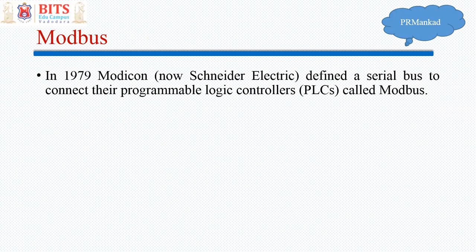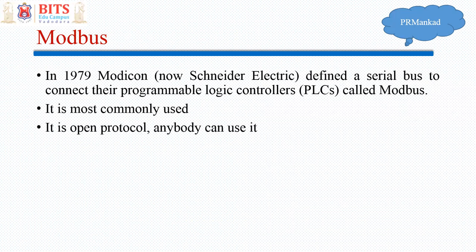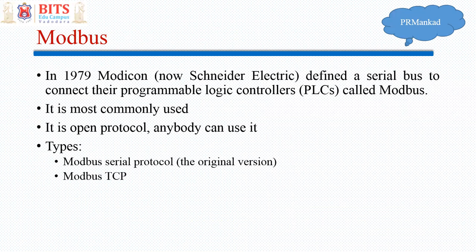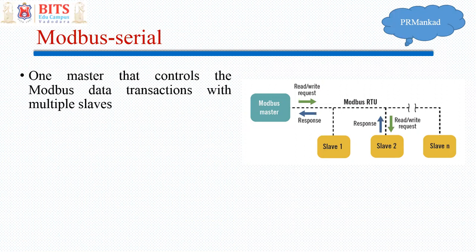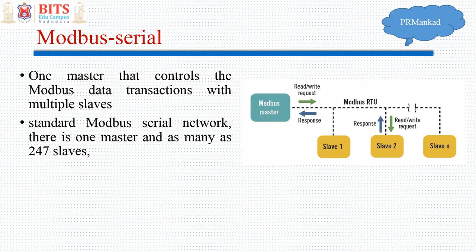Modbus was developed in 1979 by Modicon, which is now Schneider Electric, for communication between PLCs. It is the most commonly used and it is an open protocol — anybody can use it. There are two types: Modbus Serial protocol and Modbus TCP. Modbus Serial is a master-slave protocol where generally a PLC is configured as the Modbus master and sensors and actuators are Modbus slaves. One master can control as many as 247 slaves, each with a unique slave address.